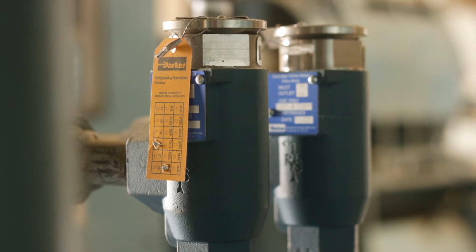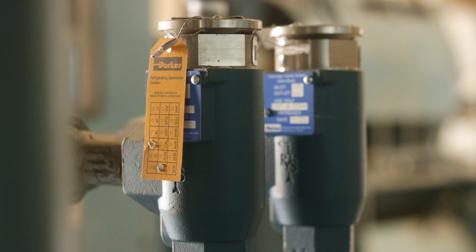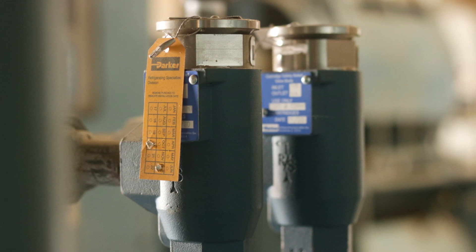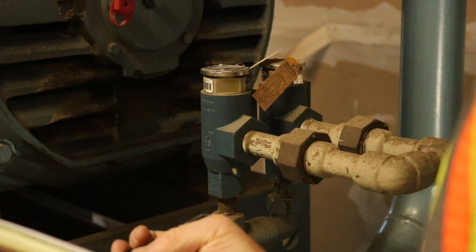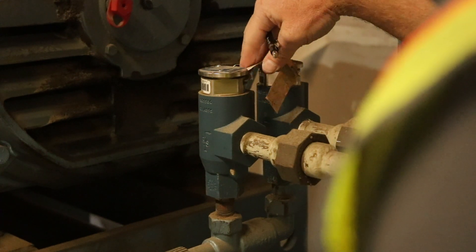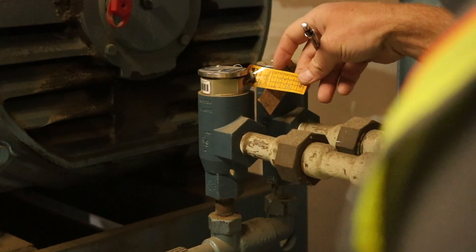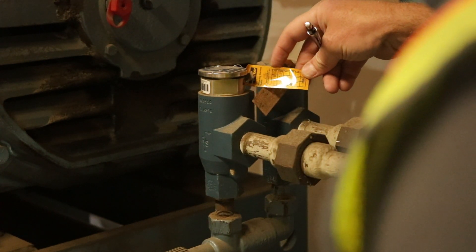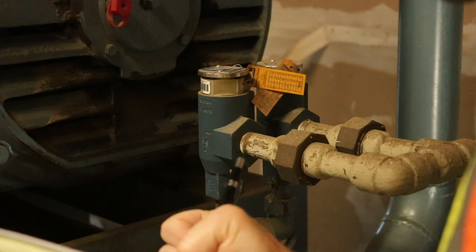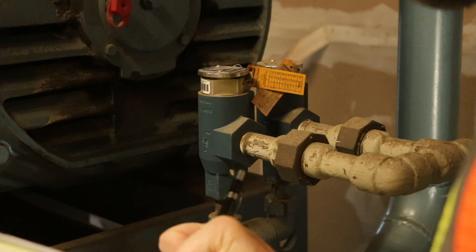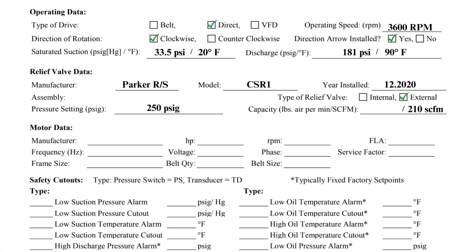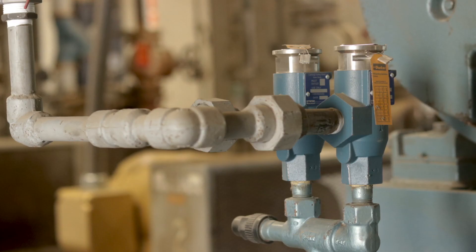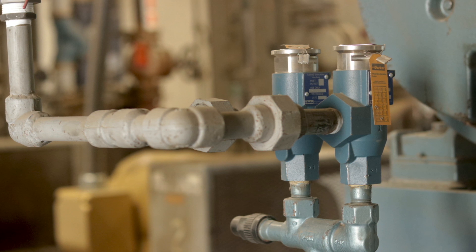Note: if your facility reprints the same completed first page for each checklist, the relief valve data is one data point on the first page that can change. Be sure to check if the relief valve installed matches what is listed on the form. The relief valves on this compressor are external to the equipment and terminate to atmosphere, so this configuration is categorized as external.